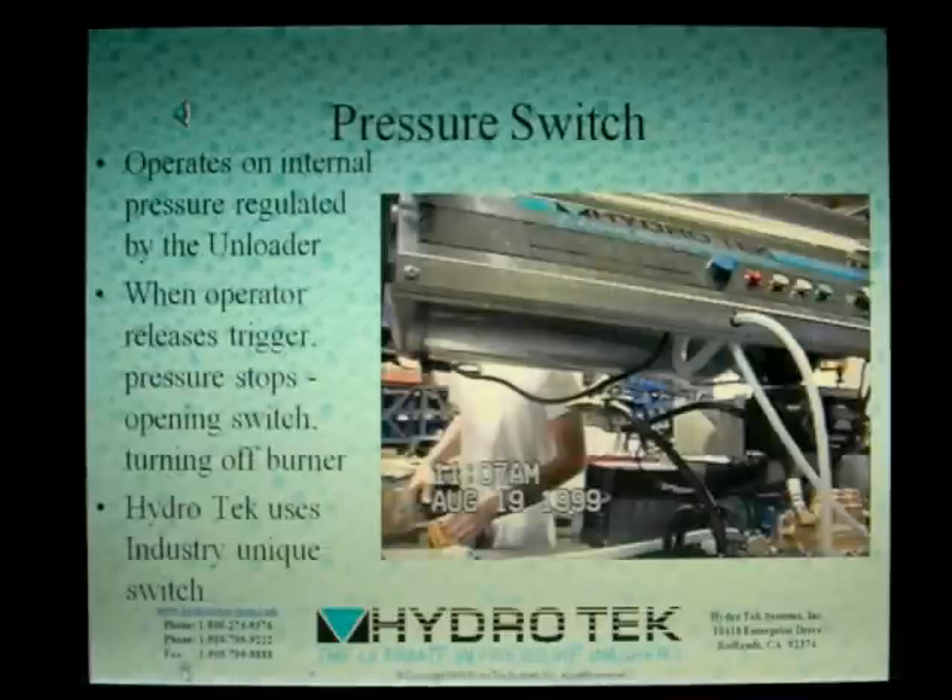In 1999, Hydro Tek began using an improved pressure switch on all models utilizing this safety feature. Used in conjunction with the flow-sensitive unloader that doesn't trap pressure, providing total relief, the pressure switch reacts to the pressure created at the unloader to control the burner's operation. When the operator pulls the trigger, the pressure switch responds and allows power to the burner.